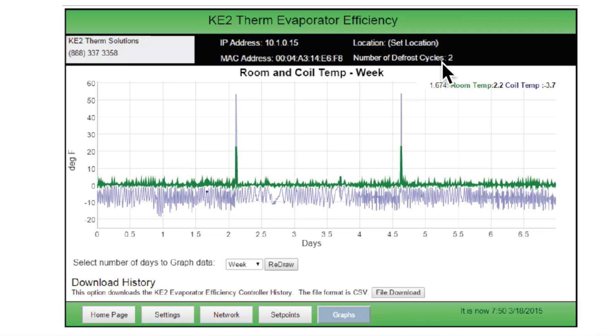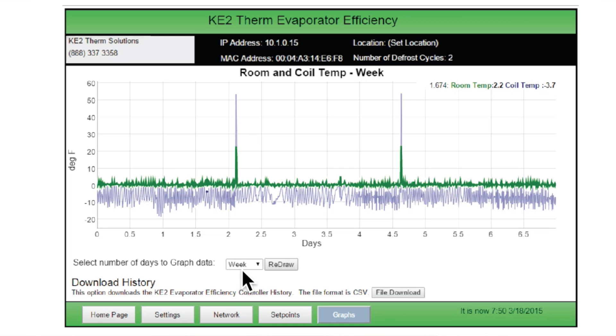Additionally, the number of defrost cycles is displayed. Here we see two defrost cycles in the past seven days shown on the graph. The graph page provides a look at room temperature and coil temperature of the controller. Along the left vertical axis of the graph is the room temperature, and along the bottom horizontal axis the days are shown. The most current data is near the origin on the left side. Graph information can be displayed as a weekly view or also a monthly view. When you select a date on the graph, the room temp and coil temp for that point in time are displayed in the upper right corner of the graph.